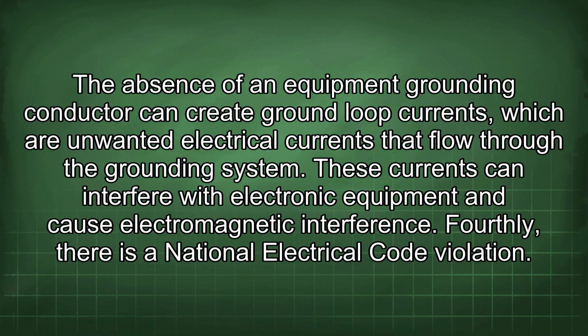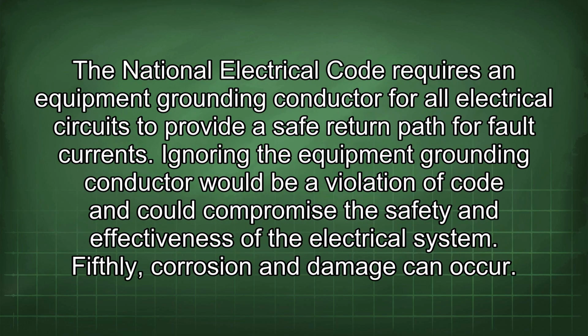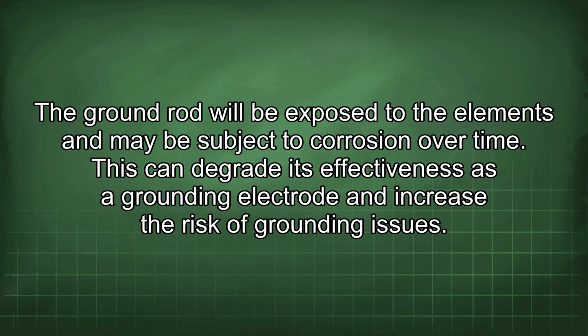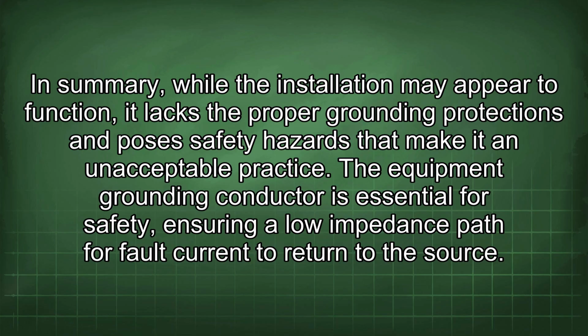Fourthly, there is a National Electrical Code violation. The National Electrical Code requires an equipment grounding conductor for all electrical circuits to provide a safe return path for fault currents. Ignoring the equipment grounding conductor would be a violation of code and could compromise the safety and effectiveness of the electrical system. Fifthly, corrosion and damage can occur. The ground rod will be exposed to the elements and may be subject to corrosion over time. This can degrade its effectiveness as a grounding electrode and increase the risk of grounding issues. In summary, while the installation may appear to function, it lacks the proper grounding protections and poses safety hazards that make it an unacceptable practice.